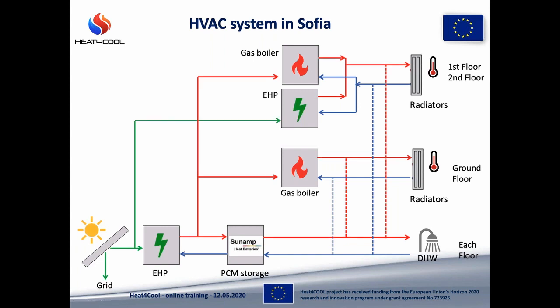So for each heating zone, the following facilities will be installed in the vicinity of the gas boilers. A two-way spherical on-off motorized zone valve implements the connections between the heat pump and the heating outlets for the given heating zone. A hydraulic separator provides for hydraulic separation between the heat pump and the heating outlets for the given heating zone.